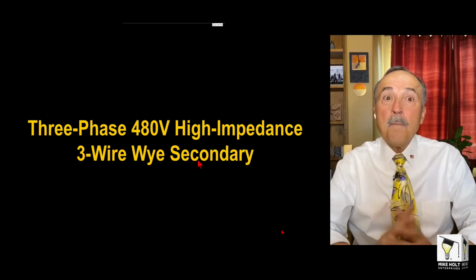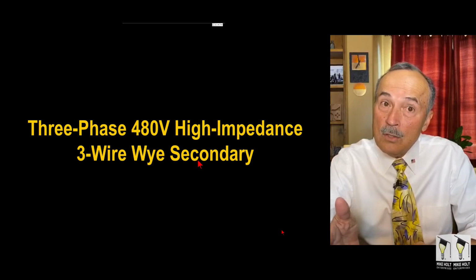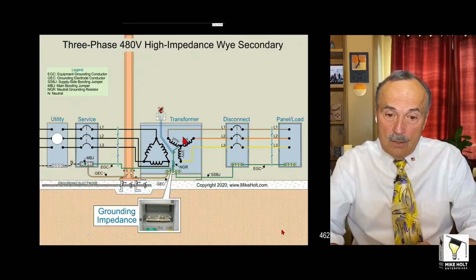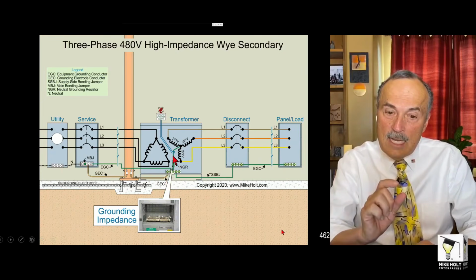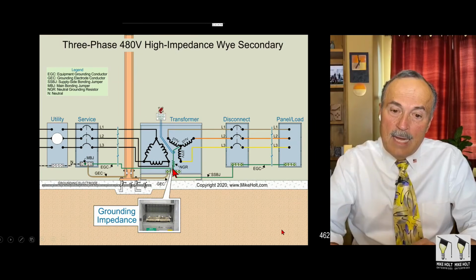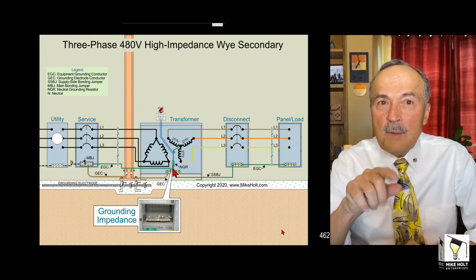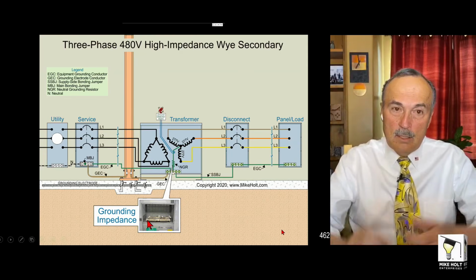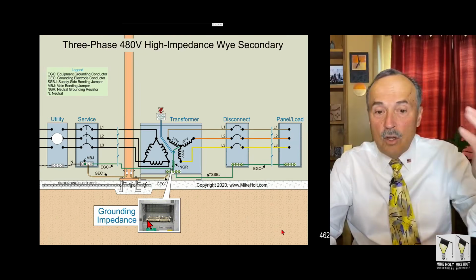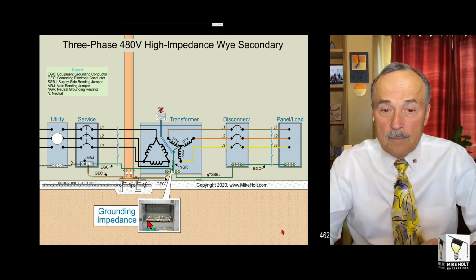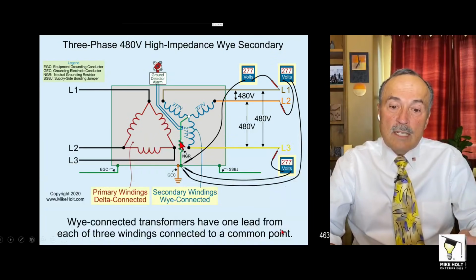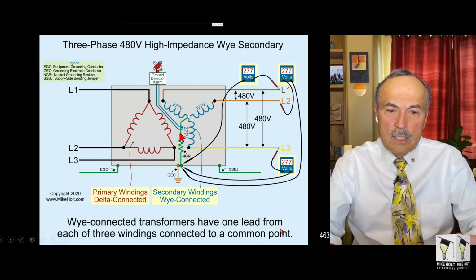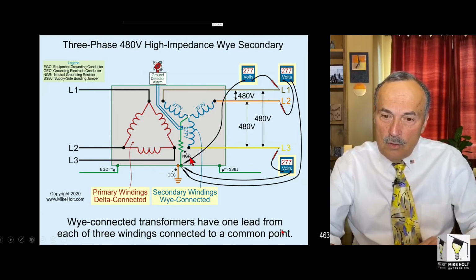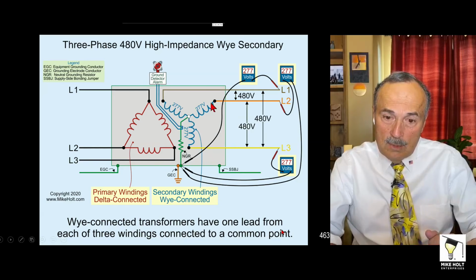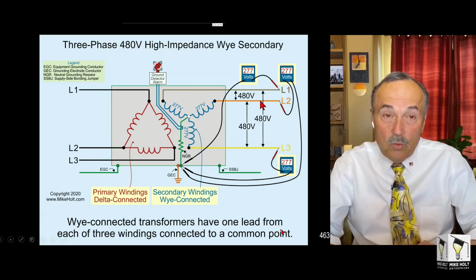3-phase, 480 volt high impedance, the best of all systems, except you don't get any line to neutral loads on the secondary, so you can't have them. So here you go right here, 277, 277, 277 per phase, and then the system bonding jumper has a resistor or impedance. It looks like this here. You can see how it's like a coil, so it heats up in the event of a fault. And then there are alarms that go off and tell you, hey, you've got a ground fault out there. So here's the alarm on it. I don't know if I said 1 ohm. It's a 277 ohm resistor for the system bonding jumper. The voltage from line 1 to here is 277, 277, 277, and this to here is the same point, 277. Voltage between the lines is 480.